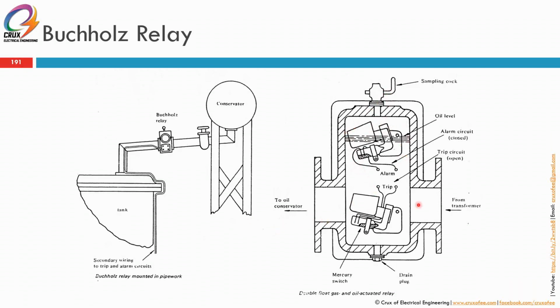So if there's any gas coming from the tank, it will come through here and fill up the top part. If it's a slow gas build up, it will go to alarm, then it will go to trip. If it's a very fast build up, like a flashover internal of the transformer, then it could trigger the trip almost immediately. Okay, so this is the alarm contact and the trip contact.